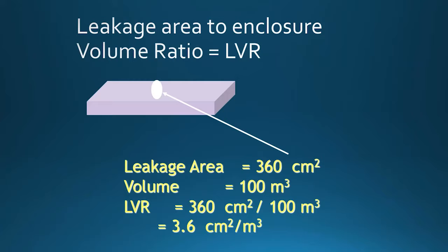We based our peak pressure evaluation on what we call the leak to volume ratio, which is kind of a surrogate for mass flow rate. Once you determine the leak to volume ratio for a certain size of enclosure, if you double or triple the size of the enclosure, it performs pretty much exactly the same way. When you double the enclosure, you put in double the gas, you need double the leakage area, and so on. The leak is measured with a door fan. The volume is just the volume of the flooded enclosure, and it's as simple as that.